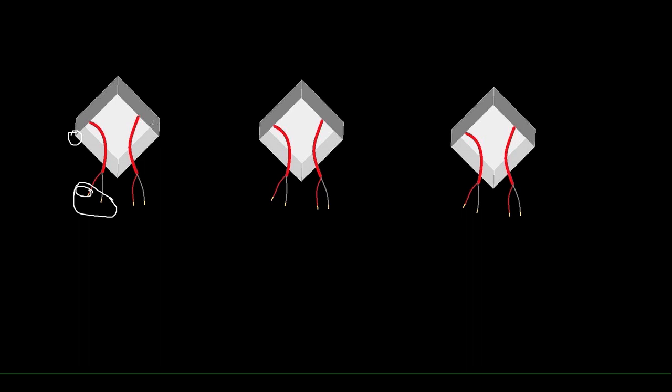In the last time that we troubleshot the open circuit, we took our meter, we metered these two wires. Let's assume we had hooked that back up so we have our three volts and our ground fault. We know it's on our red, so we can go from red, one meter lead to red, the other one to the conduit, assuming we had all these boxes connected. That's another point I guess I should make. If you're in an application where you've got just like floating cable, you may not have a great ground reference. Like if these junction boxes are mounted to, let's say, wood, you might not trust you're going to actually be using some other ground reference like a nearby sprinkler pipe or door frame or something, and that makes it a little bit tricky.